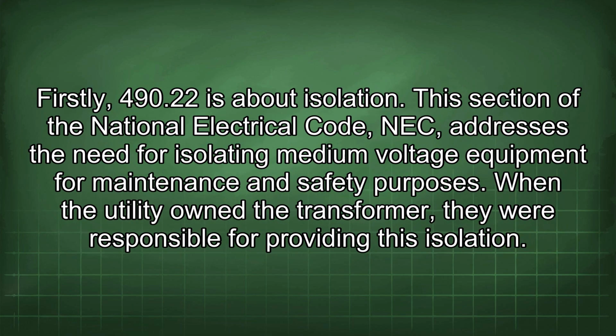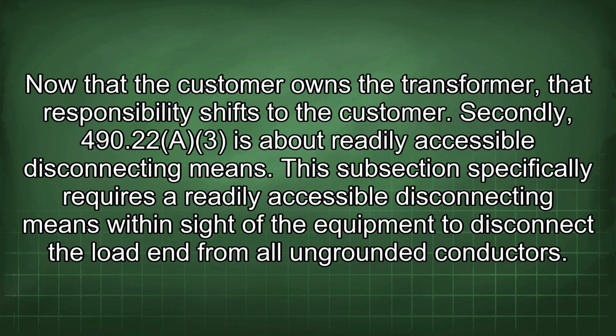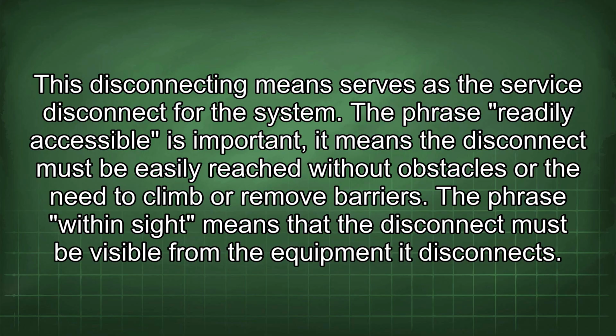Firstly, 490.22 is about isolation. This section of the National Electrical Code, NEC, addresses the need for isolating medium voltage equipment for maintenance and safety purposes. When the utility owned the transformer, they were responsible for providing this isolation. Now that the customer owns the transformer, that responsibility shifts to the customer. Secondly, 490.22 is about readily accessible disconnecting means. This subsection specifically requires a readily accessible disconnecting means within sight of the equipment to disconnect the load end from all ungrounded conductors. This disconnecting means serves as the service disconnect for the system.